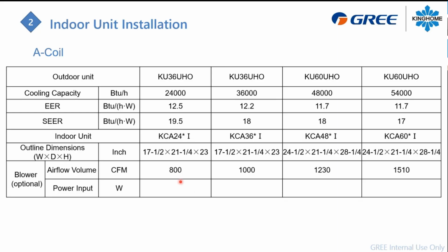So 800 CFM for a 2 ton. You cannot do less than 1,000 for a 3 ton, 1,200 for a 4 ton, and 1,500 for a 5 ton unit.